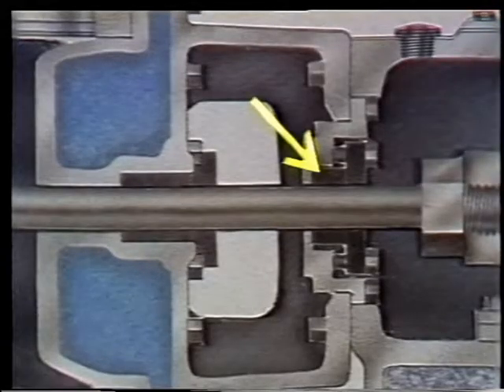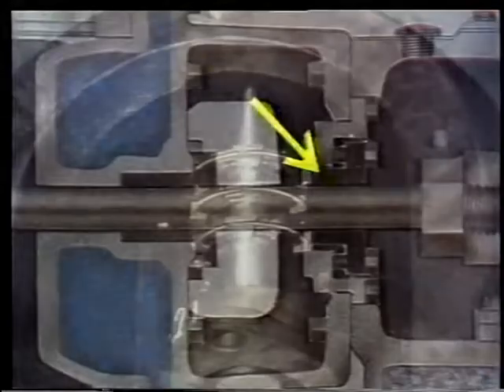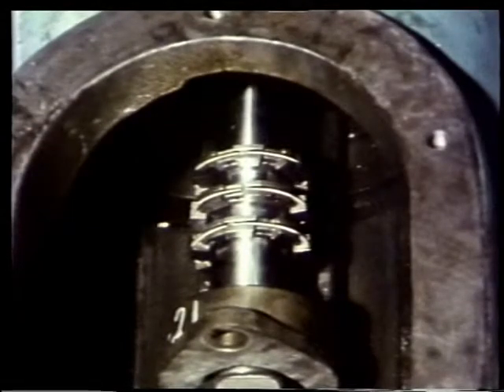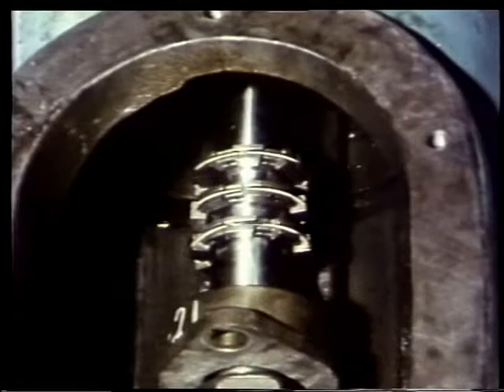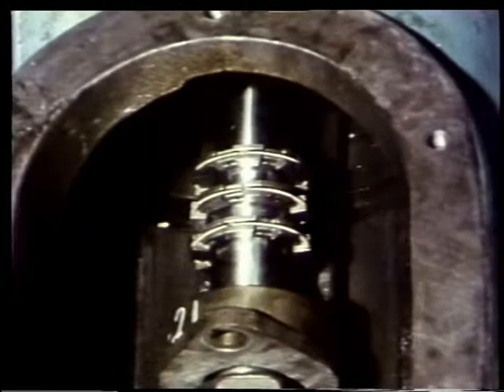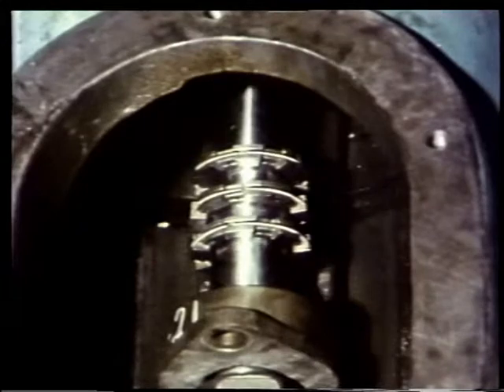Further along the piston rod, we come to some oil wipers. Each oil wiper is made up of a series of thin blades that are held against the piston rod by a set of springs. The blades seal around the piston rod to keep crankcase oil in the crankcase.